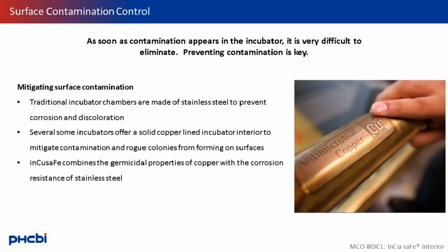Some companies have decided to use copper instead of stainless steel to create a premium option for cell culturists who are concerned with contamination. Metallic copper surfaces kill bacteria, yeasts, and viruses. Having a completely copper interior can be beneficial in that it mitigates contamination. The major issue with these interiors is that they do easily corrode and become extremely difficult to clean and keep in good conditions.